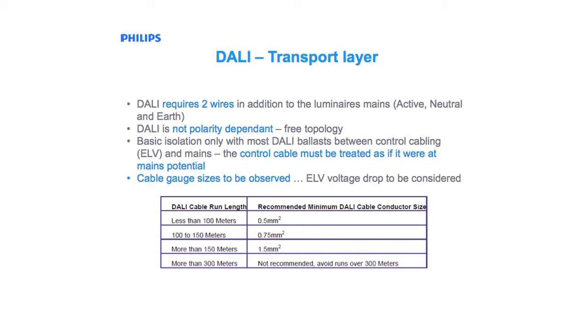network. The DALI system requires 2 wires additional to the mains power as a transport layer, so running parallel to the mains power cables into the fittings will be an additional 2 wires of cable. These additional wires carry the DALI protocol. DALI is not polarity dependent, so the 2 wires can actually be wired either way, positive-negative or negative-positive. There is a requirement for the gauge size of the cable depending on the length of run. DALI cannot be run more than 300 metres in one particular universe. If more than 300 metres are required, it is recommended that a DALI network repeater be used.